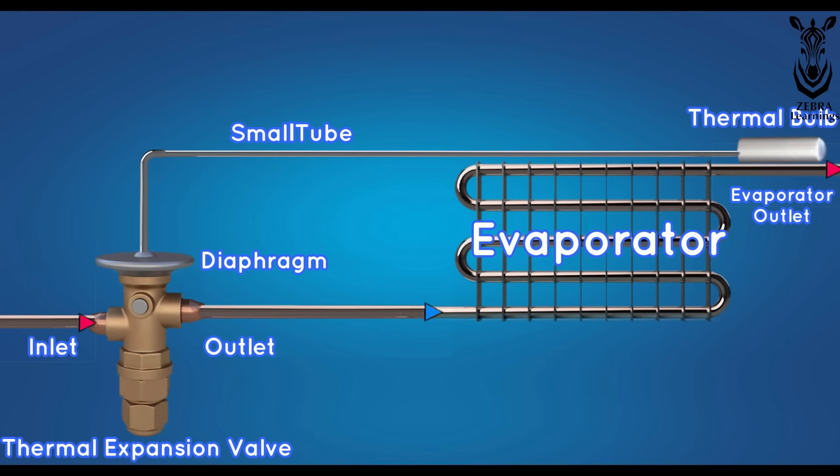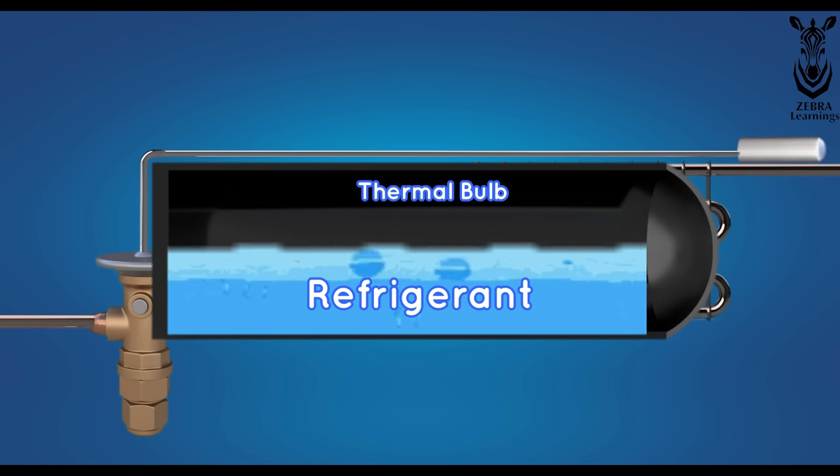The refrigerant that enters the evaporator is heated and converted into vapor and exits. When the outlet heats up, heat is transferred to the thermal bulb. At that time, the refrigerant inside the thermal bulb will begin to boil and turn into vapor.